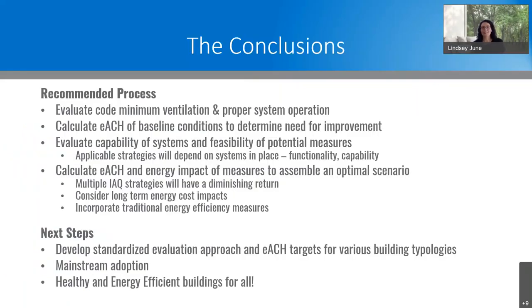So these studies showed that it is possible for buildings to operate in a manner during epidemic conditions that reduce airborne transmission risk without a significant impact to energy use and cost, relative to the ASHRAE COVID operations guidance that these studies followed. And this can be done by implementing a smart combination of measures around the primary focus of these studies, which was ventilation, air cleaning, controls, and filtration. So insights presented here today into the analysis methodologies and the measure considerations can act as a starting point for further investigation in identifying the combination of strategies best suited for your building. There's many more details, resources, and takeaways within the individual study reports themselves that are posted on our FlexTech IAQ webpage. We'll also be adding case studies and final conclusion reports in the next few months, so check back for that additional information.